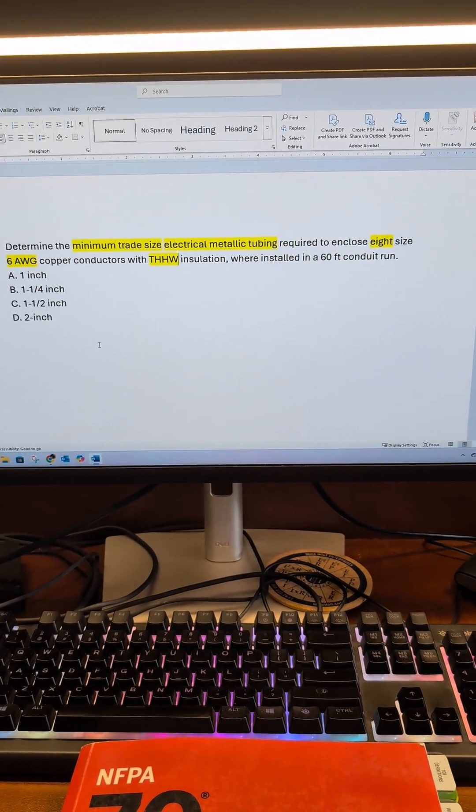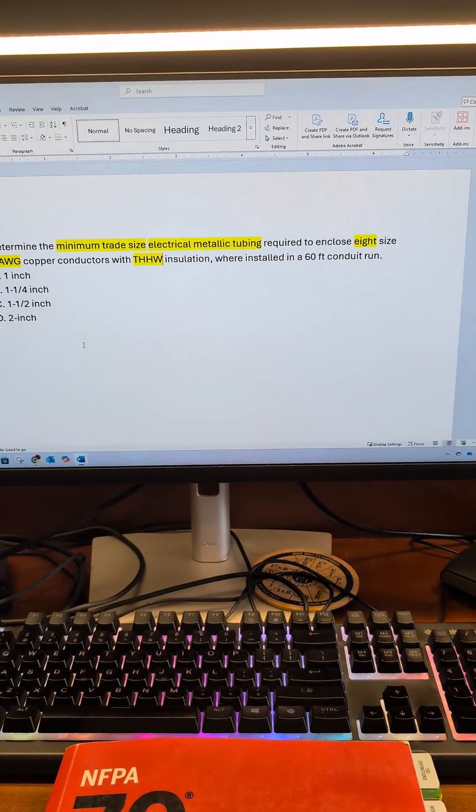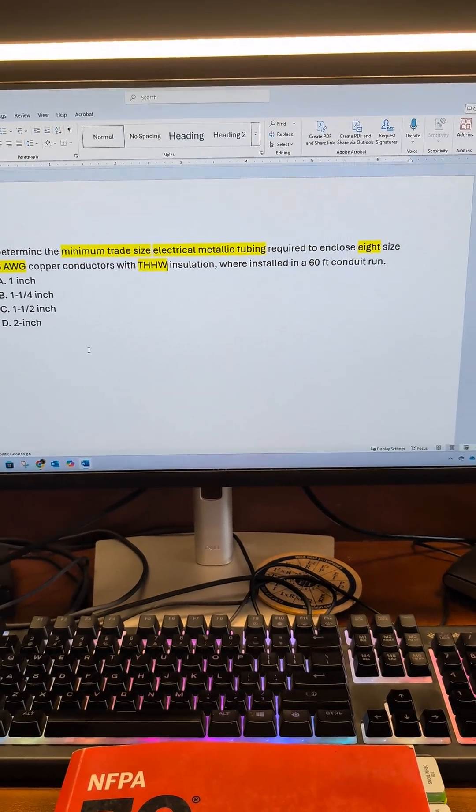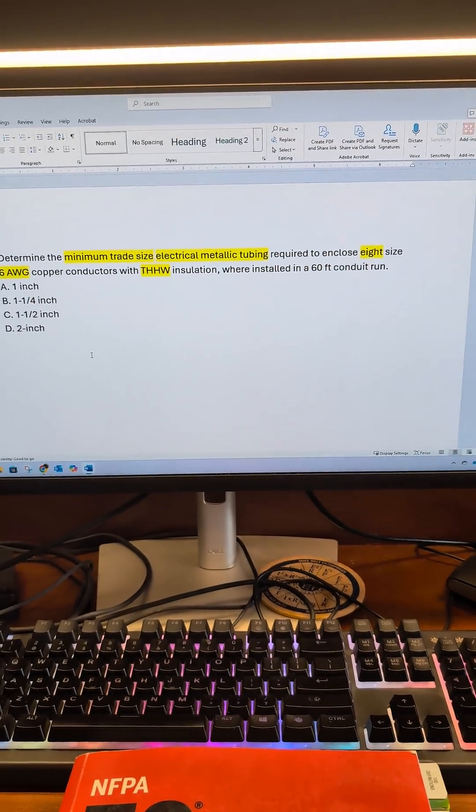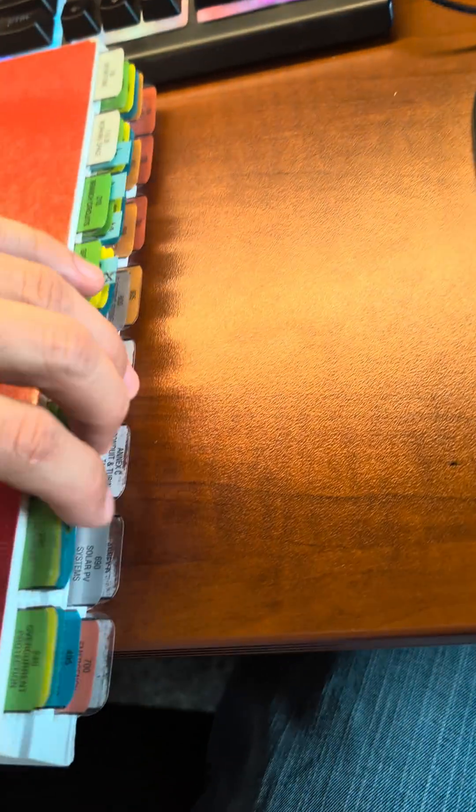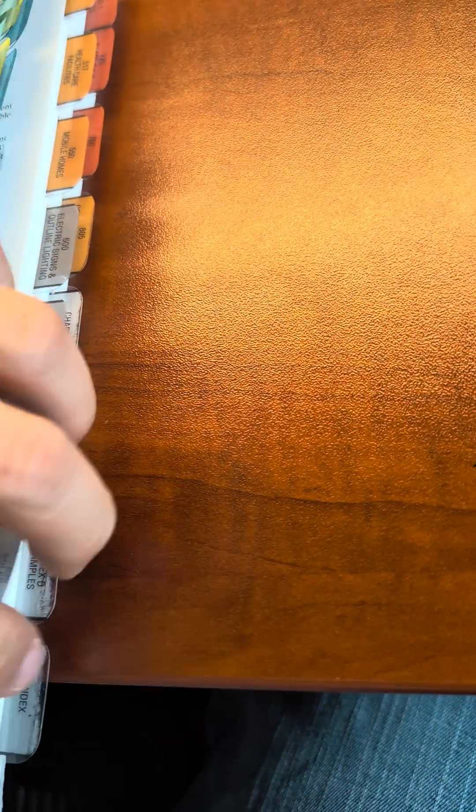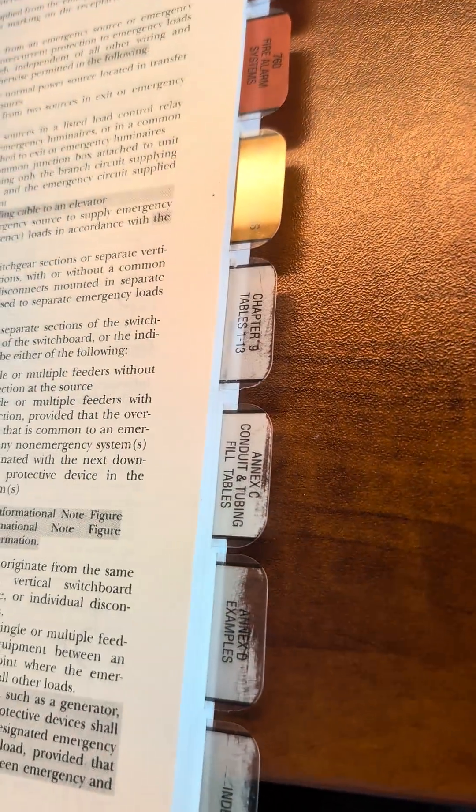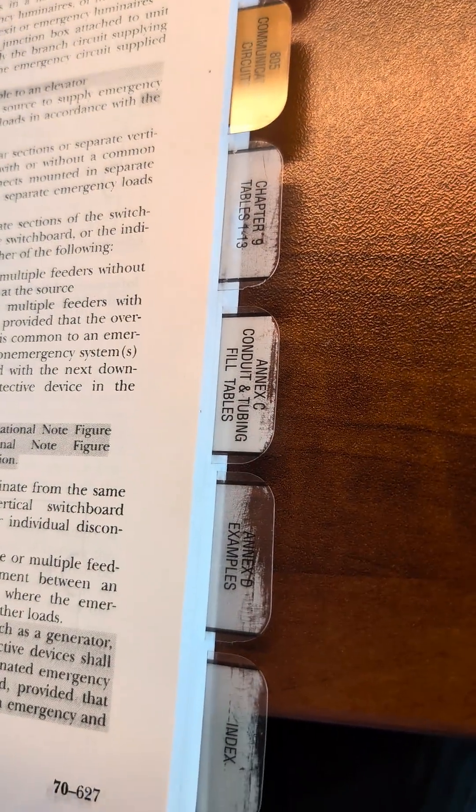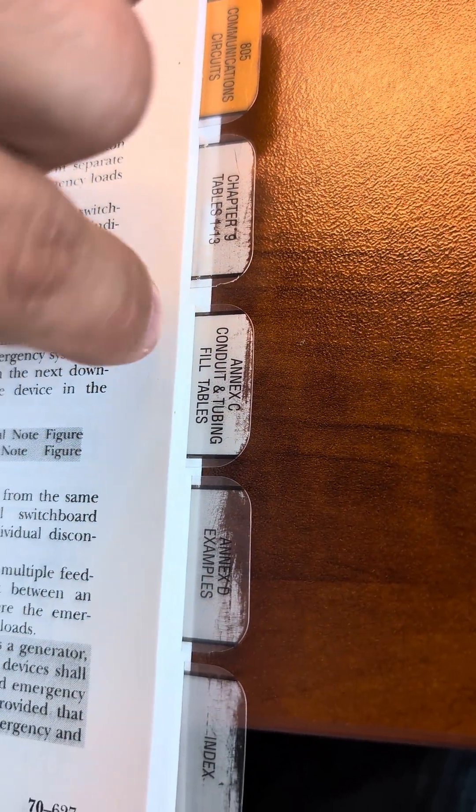There's two different ways you can do it using either Annex C or Chapter 9, Tables 5 and Tables 4. So if you don't know, in the back of the book, you should have a tab that's called Annex C, Conduit and Tubing Fill Tables.